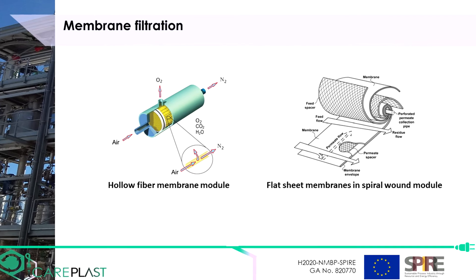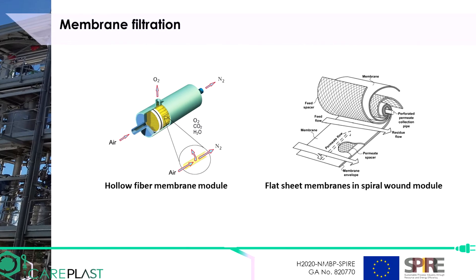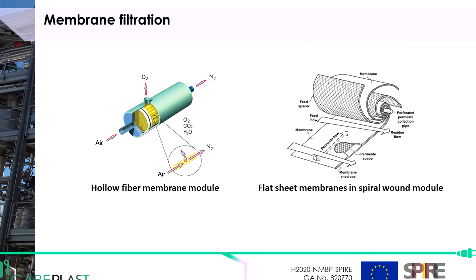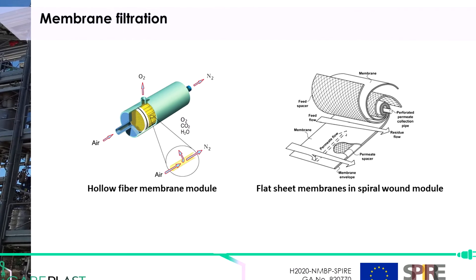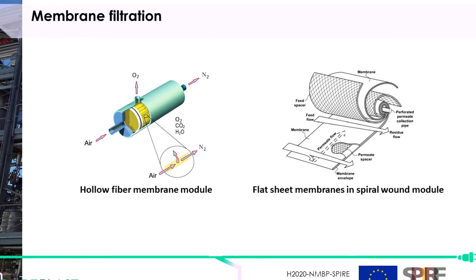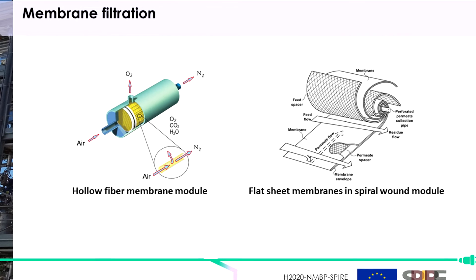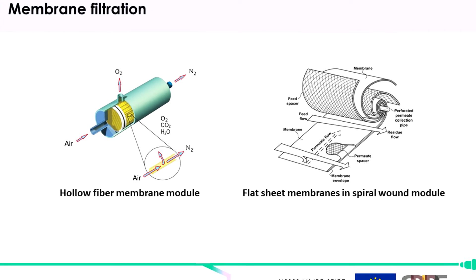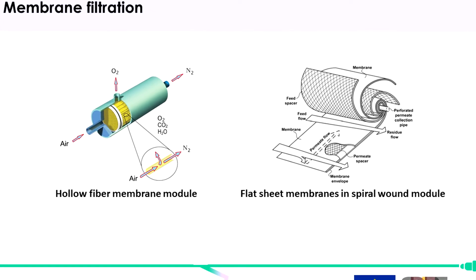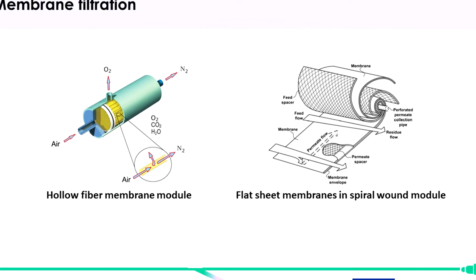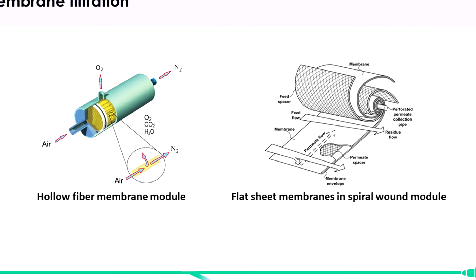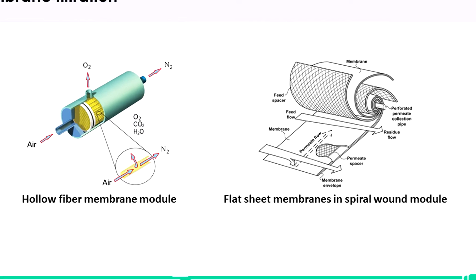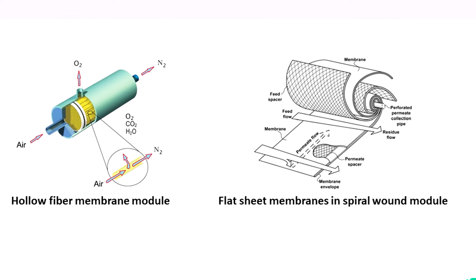There are two main types of membranes. Hollow fiber membranes, which essentially are straws with on one side the feed and on the other side the permeate — these can generally be operated both inside-out and outside-in. And second, flat sheet membranes. These flat sheets are rolled into spiral wound modules, allowing for a large amount of membrane surface area to be packed in a small volume.